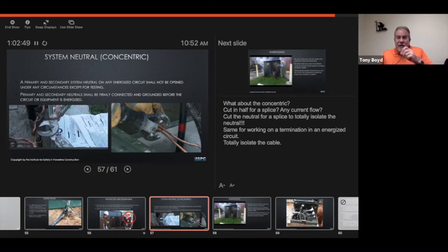And then on the overhead system, if you remember several years ago, the ground wire that came down the pole actually had a little U-shaped cover, whether it be wood or plastic, on top of it. What do you think that was for? That was to protect the public from coming in contact with that ground wire, which is connected to the system neutral, which is carrying current. So we've determined over time that the current level is so small, so slight, that it's not really a hazard to the public any longer. However, if we have a car hit the pole and one of the conductors comes down and energizes that neutral, it also energizes that ground wire. So that's where the hazard is.